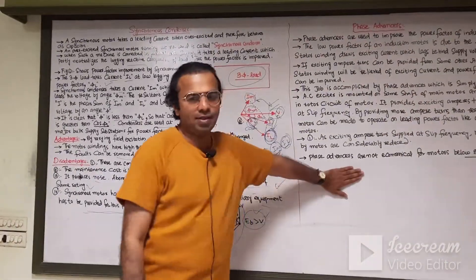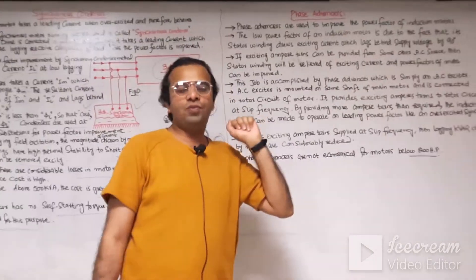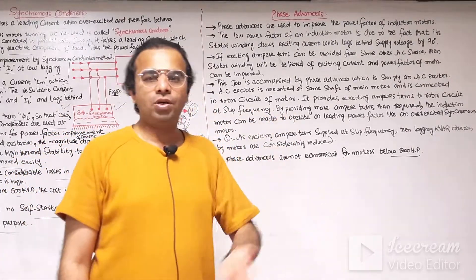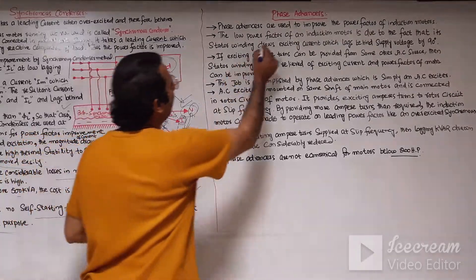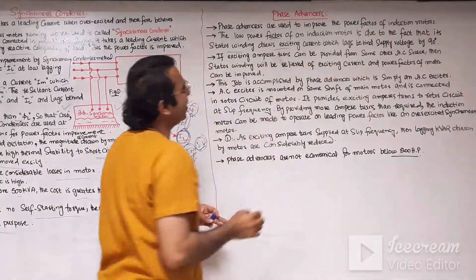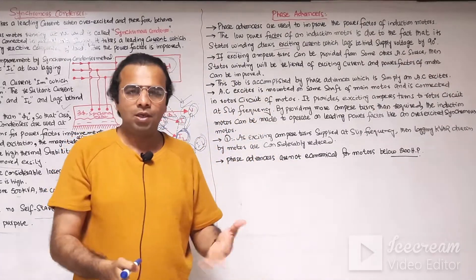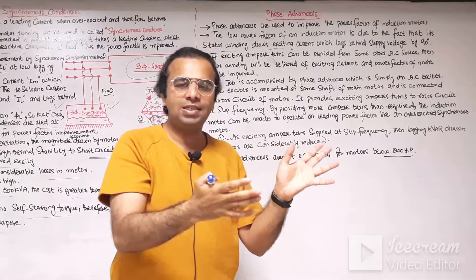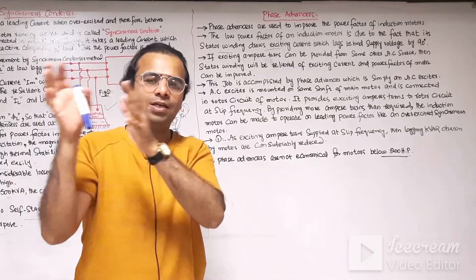The second method is the phase advancer. Phase advancers are used for the power factor improvement of the three-phase induction motor. The three-phase induction motor has two types of rotors: squirrel cage or wound rotor. Phase advancers are used to improve the power factor of induction motors. The low power factor of the induction motor is due to the fact that the stator winding draws an exciting current which lags behind the voltage at an angle of 90 degrees. The stator of the three-phase induction motor is energized from the main three-phase supply, producing a three-phase revolving magnetic field that runs at synchronous speed.